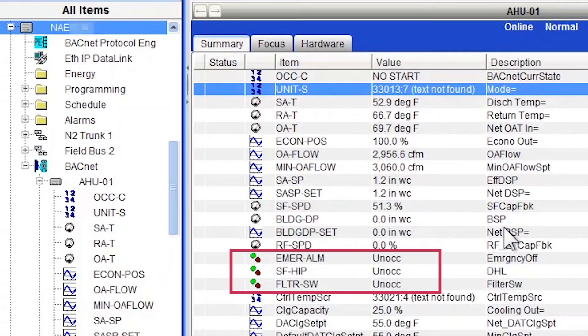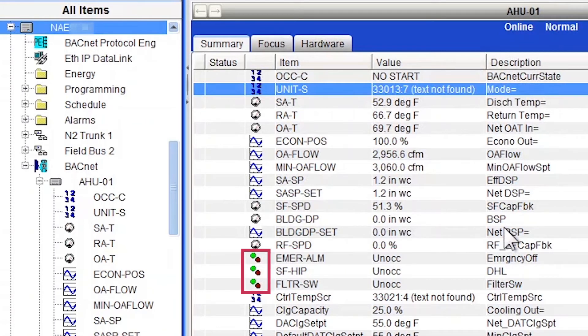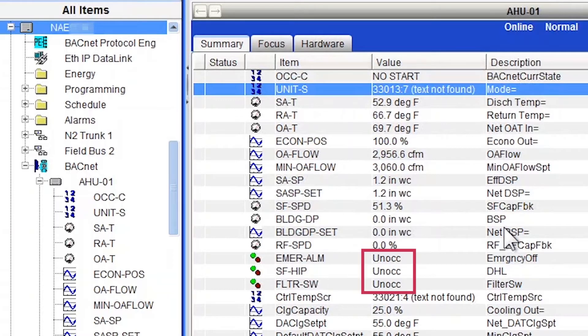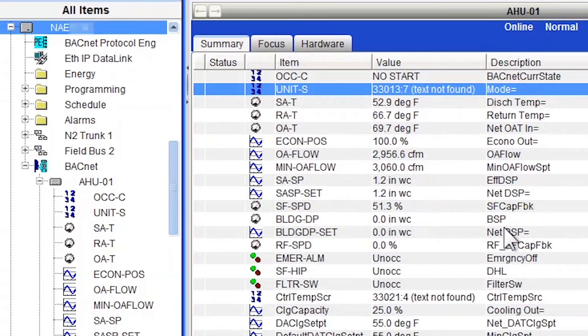And next we have a group of binary inputs. You can tell by looking at the little icon. It has like a green and red status light. And they show the units of unoccupied, which they should be something more like normal alarm, or off on. So let's take a look at them closely and see how they get fixed.